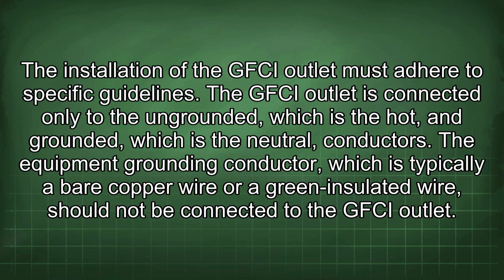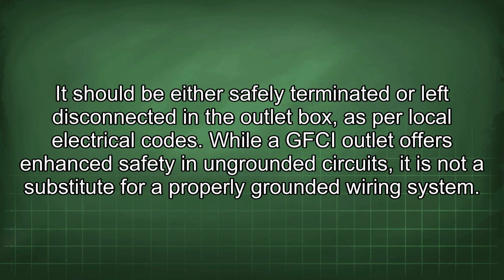The GFCI outlet is connected only to the ungrounded, which is the hot, and grounded, which is the neutral, conductors. The equipment grounding conductor, which is typically a bare copper wire or a green insulated wire, should not be connected to the GFCI outlet.